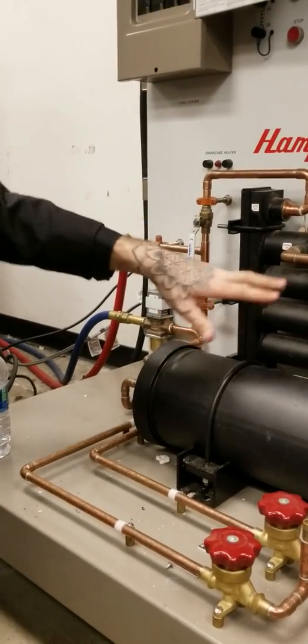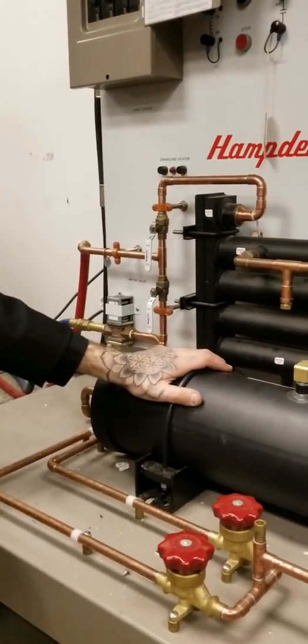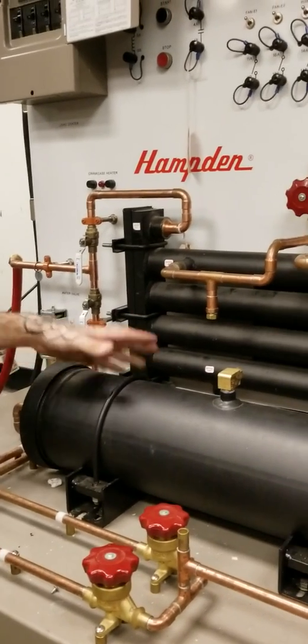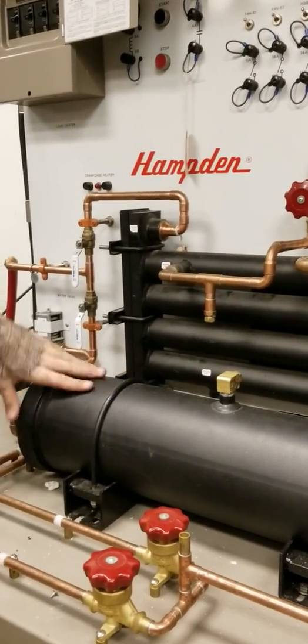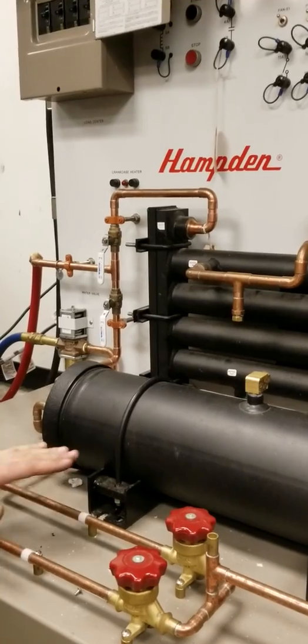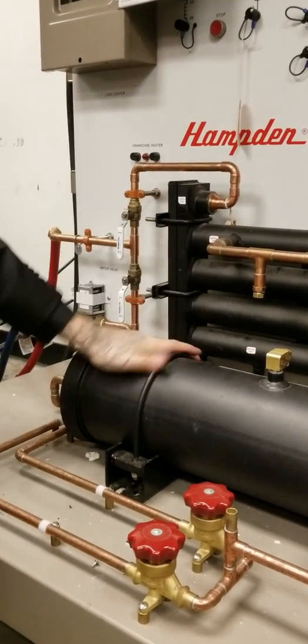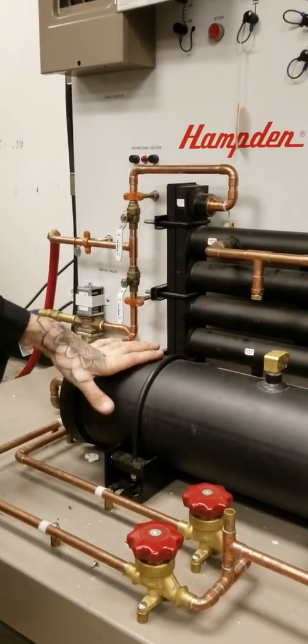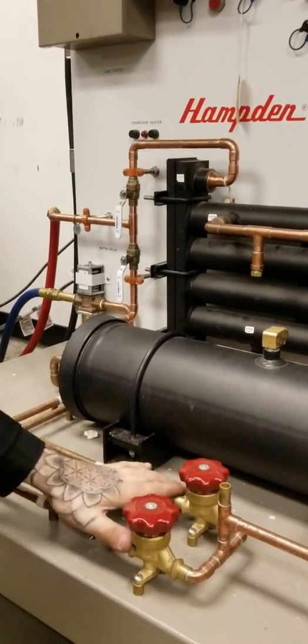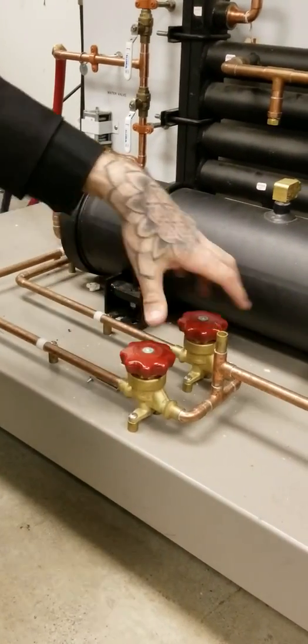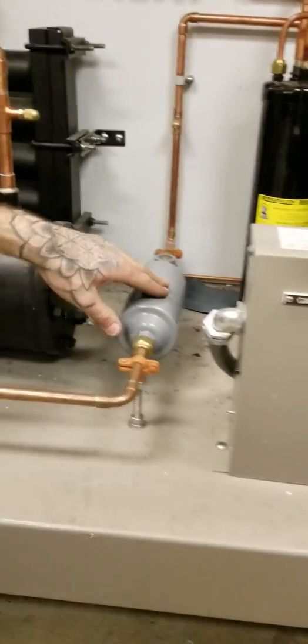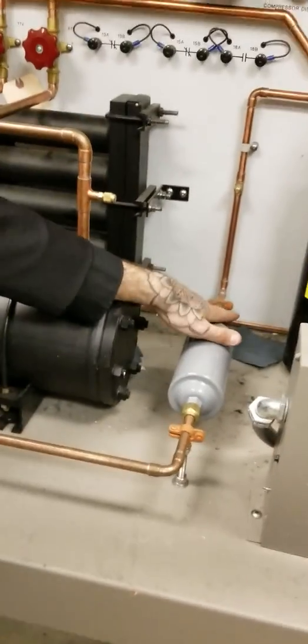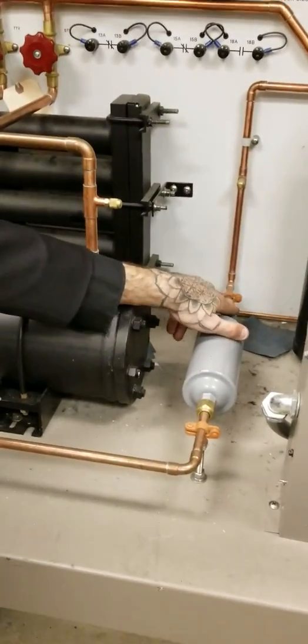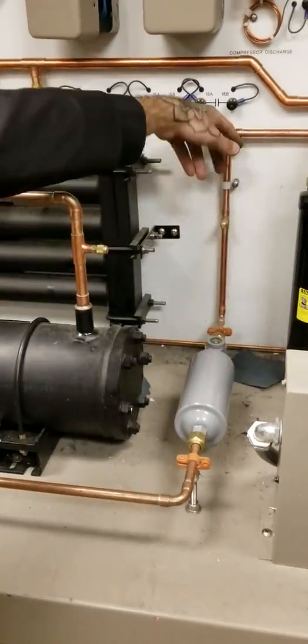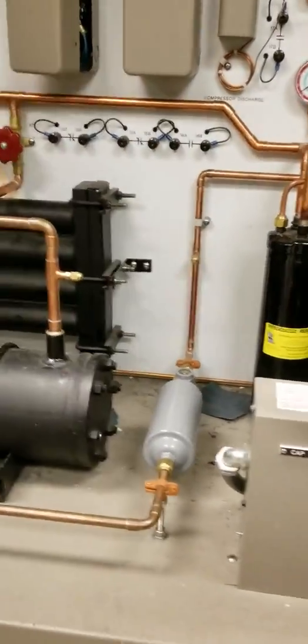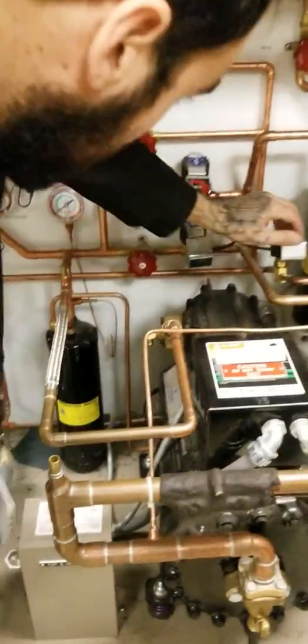So our refrigerant is going to be cooled down just like a condensing fan would, right? But we're using a water source. So our refrigerant, these are for each of our different receivers, or our condensers. And your refrigerant will then be subcooled, travel through our valves here, go through a filter dryer where we have a sight glass to indicate if we're contaminated or if we have moisture.